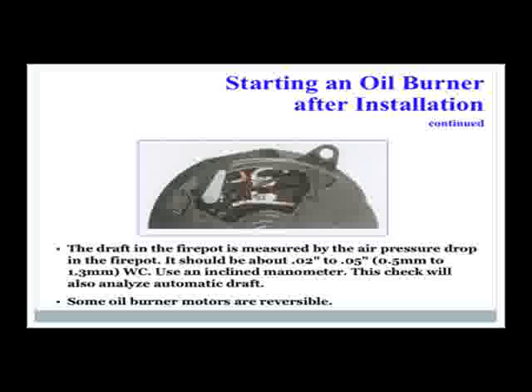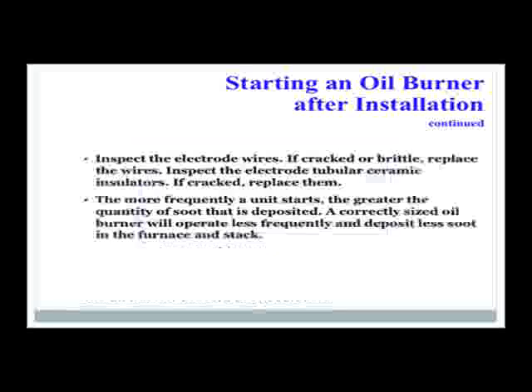Some oil burner motors are reversible. Make sure that they are blowing in the right direction. If your pump is trying to put out oil through the suction side rather than suck it in, your burner motor's backwards. Inspect electrode wires. If cracked or brittle, replace the wires. Inspect the electrode ceramic insulators. If cracked, replace them. The more frequently the unit starts, the greater the quantity of soot deposited. A correct size oil burner will operate less frequently and deposit less soot in the furnace and stack.